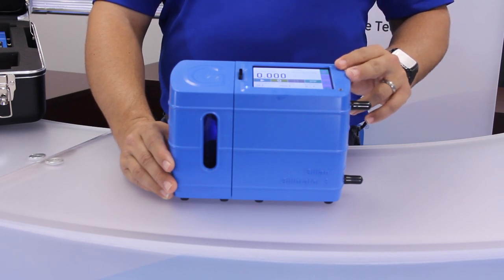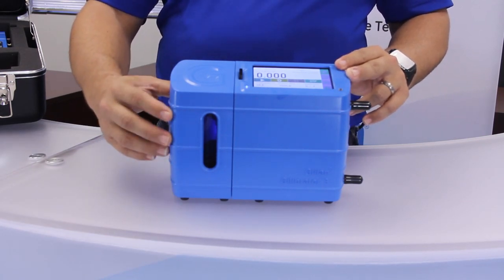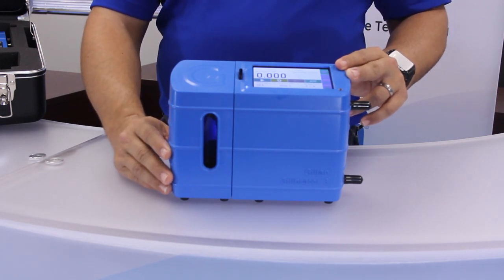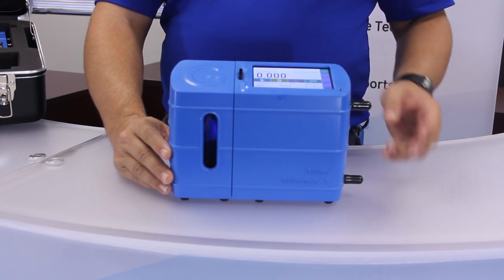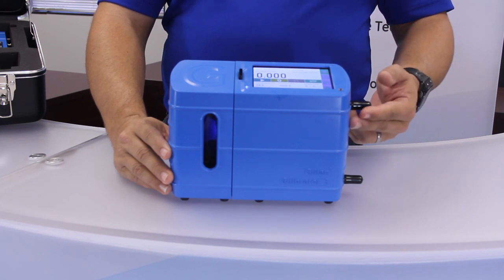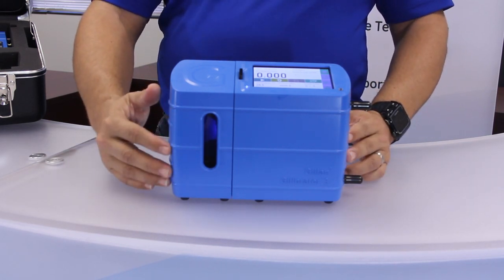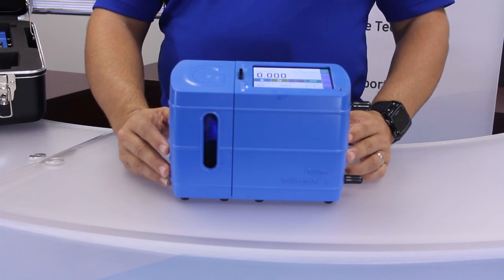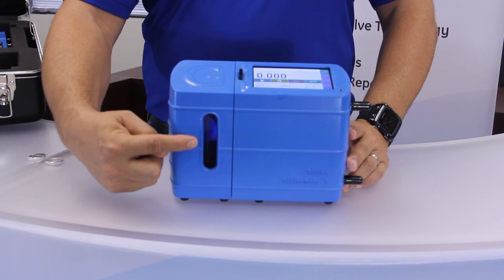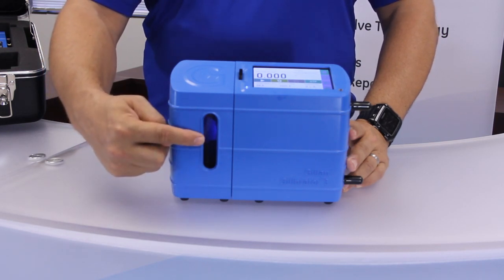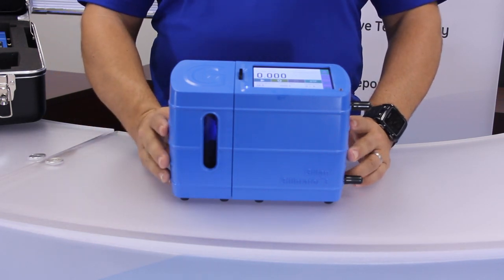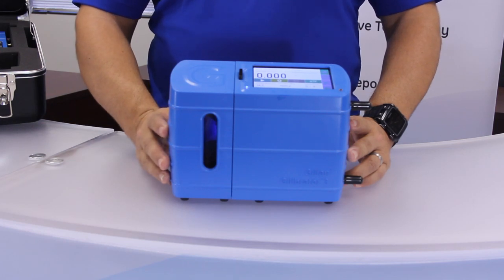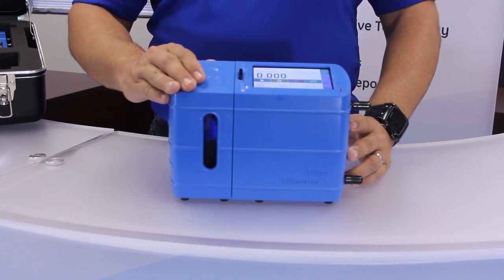The valve stuck error is tripped if the valve inside the base unit cannot get in position within a certain amount of time. This can happen if the internal pressure drops below 25 inches of water, which is possible with high flow rates on the outlet port and additional flow restrictions to the inlet port. If the puck becomes stuck inside the flow cell due to moisture aspiration, it must be returned to Sensidyne for service. Direct sunlight on the unit may trigger the internal optical sensors and cause the cell to be reset or produce an inaccurate reading. The Gilibrator 3 is only affected by high-intensity infrared light, so while it can operate outdoors, it should not be done directly in the sunlight and should be performed in the shade.